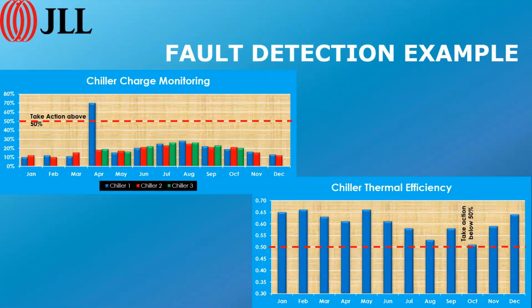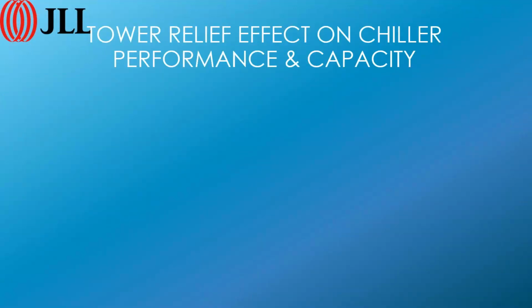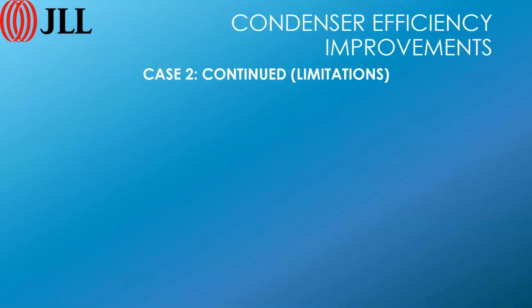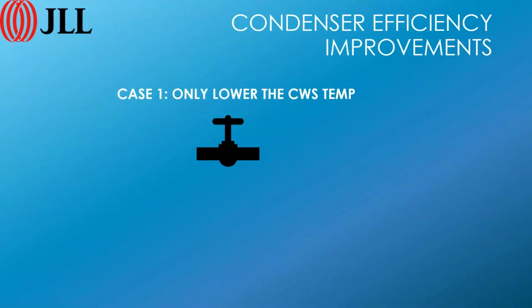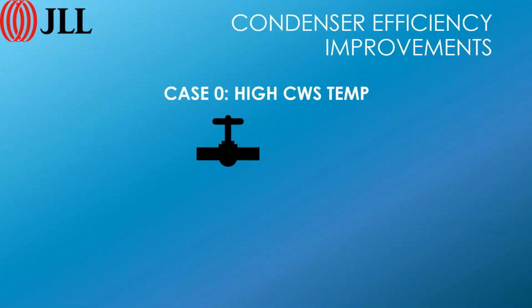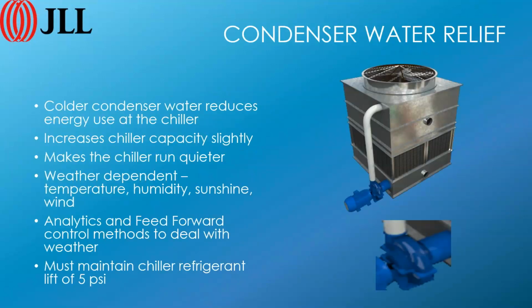Okay, so to me, what I learned here, some of the stuff was beyond me, but some of it was like, wow, I didn't realize this. My initial question before you started speaking is, why would you reduce the condenser water flow? If it's on a VFD, I never understood why you would want to reduce the flow. Well, now I understand why. You called it condenser pressure is not enough? The condenser in the chiller itself, the pressure is too low. Right. Chiller guys call it lift. The lift is the pressure between the evaporator and the condenser. You need about 5 psi for that to work.